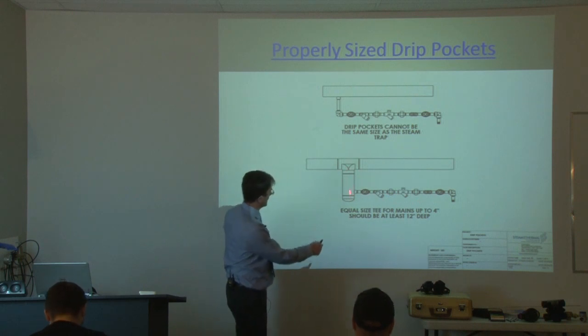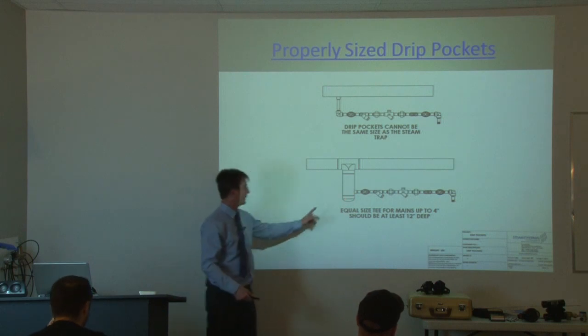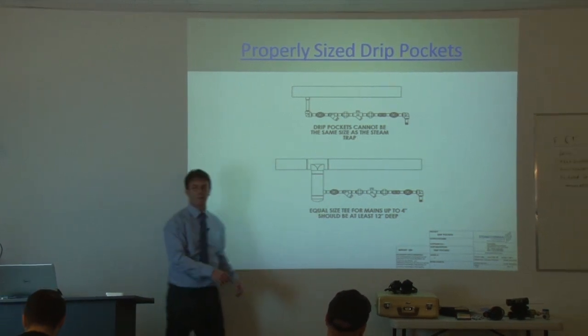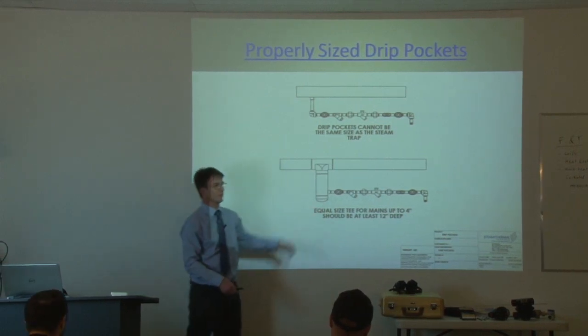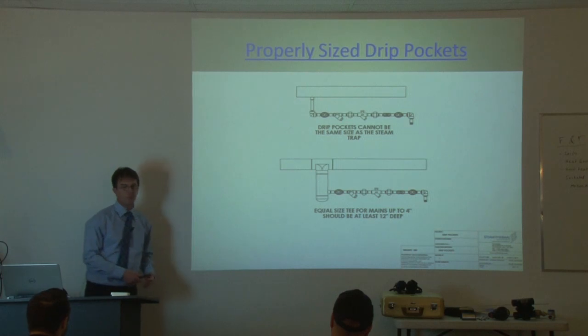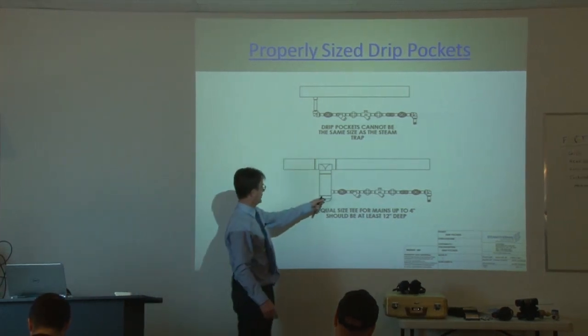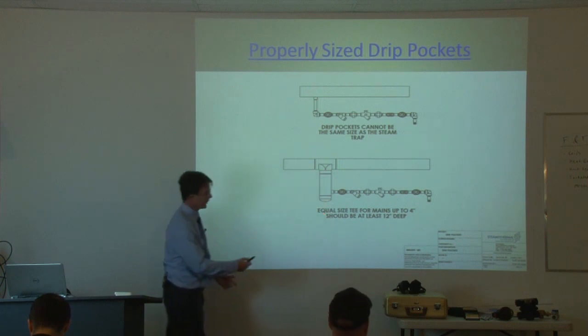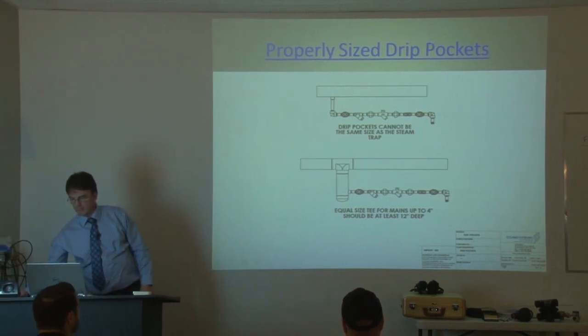So your drip pocket, this part is what we call a drip pocket, and underneath is what we call a dirt pocket. Normally, we'd want to see a valve. So we put a valve underneath, and that allows you to blow down any dirt that accumulates. Because steam pipes are dirty, a lot of times they degrade over time, and you'll have debris that builds up in your dirt pocket. So if you have a valve here, the pressure behind it will allow you to just blow down the junk that builds up in there.